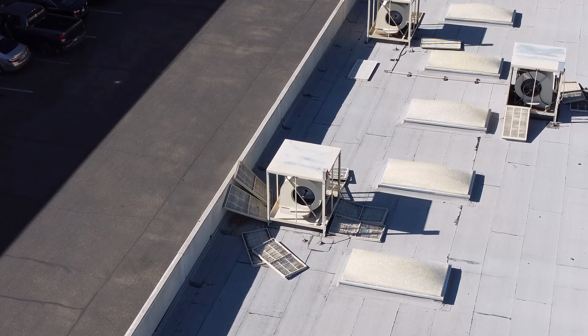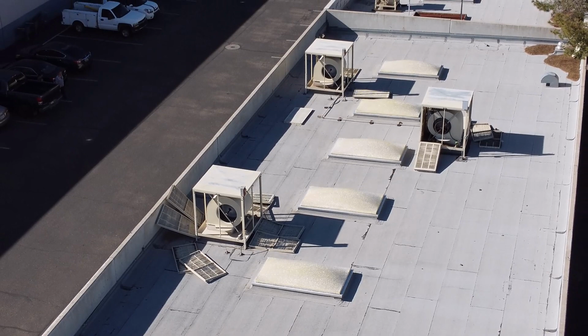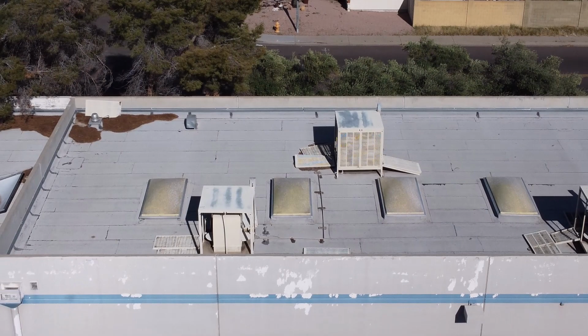So you want to just put pads in, put the panels on, oil the bearings, set the float, hopefully belt, all that stuff, and start them up. So somebody, other than those panels are just kind of left wherever, maybe the winds rearranged them, but these almost look like they were shut down. And then we get the other sides and see if the belts are removed by any chance. Some people don't remove the belts, because sometimes they'll say, hey, do you want me to leave the old belts on? That way you can at least run the vent mode for the rest of the year, just in case you get a warmer day, and some places choose to do that.